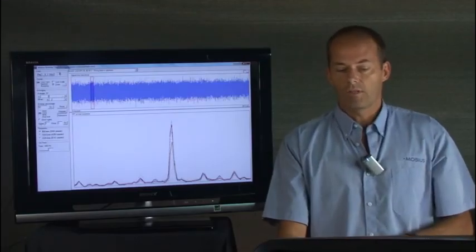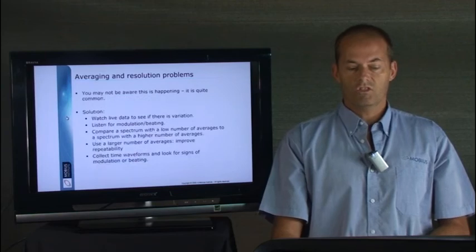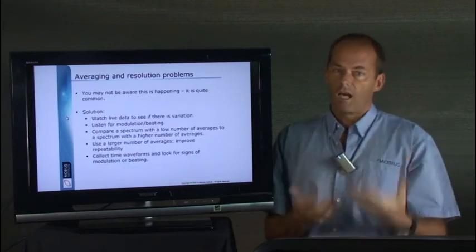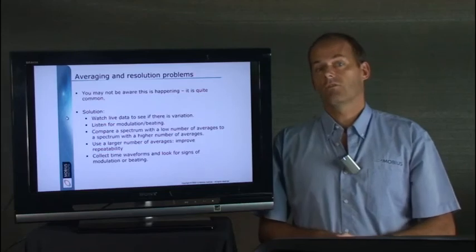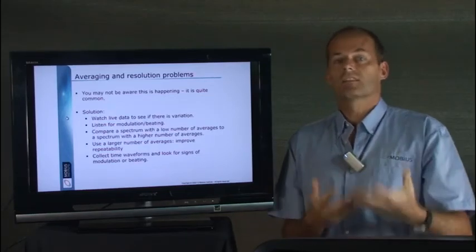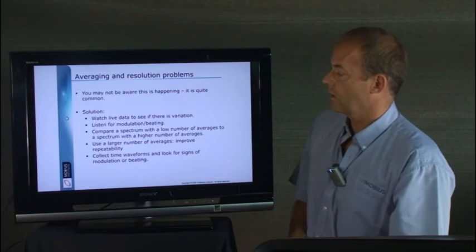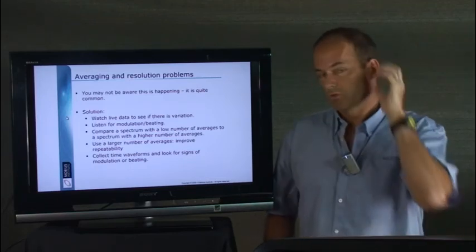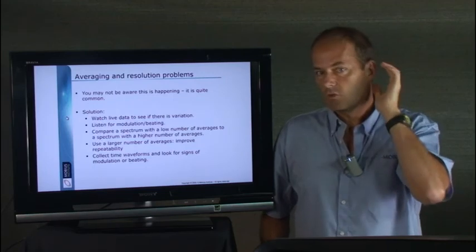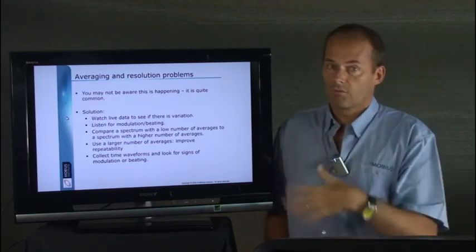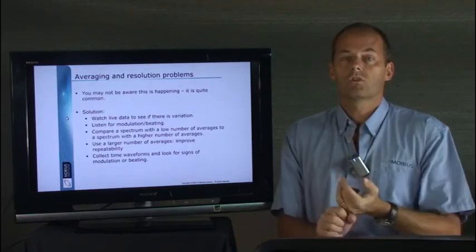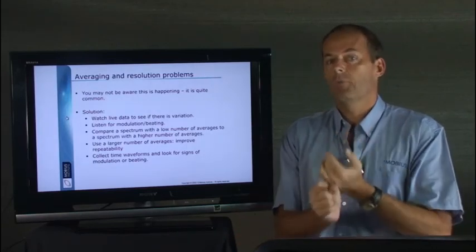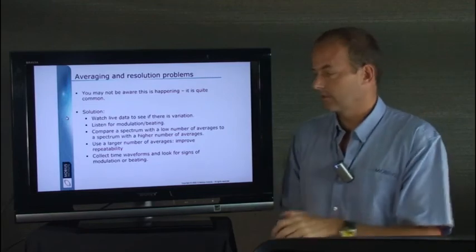I hope that demonstration didn't confuse too much and just helped you understand that there is a lot of variation in your vibration and the averaging can mislead what's really going on with the machine. So what do you do if you suspect it? Well, certainly if you hear any beating, if you hear that sound, then you know that's what's going to happen inside your spectrum. So one solution is to have a larger number of averages and it will be repeatable at least.